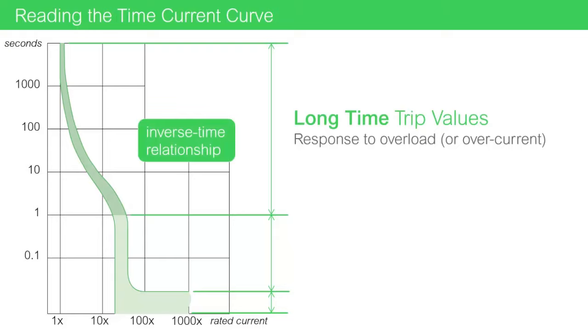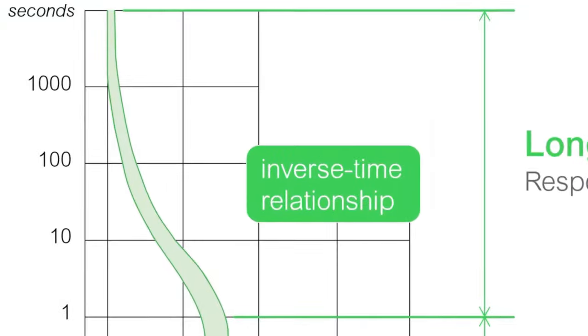You'll notice the long time trip curve has an inverse time relationship. That means, for this range of the time-current curve, the lower the current, the longer the response. The higher the current, the shorter the response.